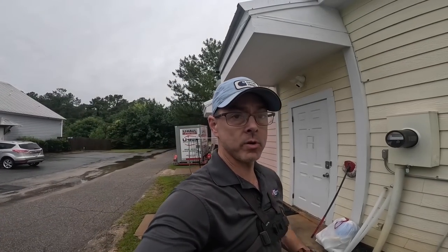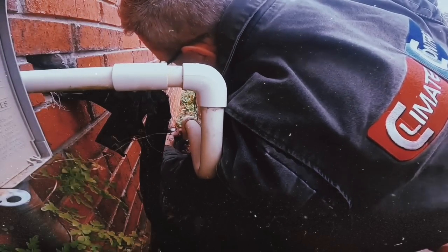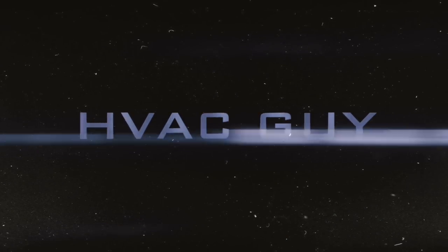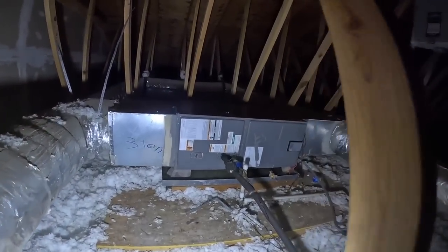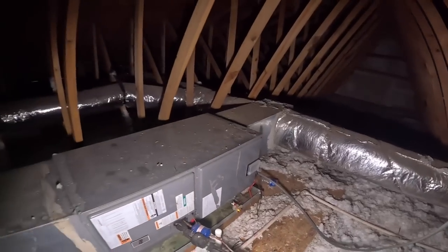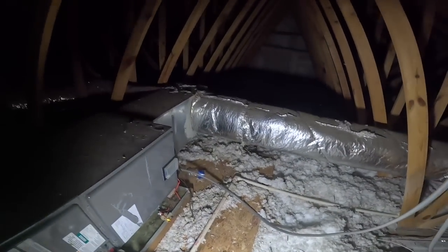Hey guys, today we've had a slight break in the rain. I've only been able to do one other call indoors — this one is running outdoors, let's check it out. I guessed right: we've got water in the emergency drain pan. This ain't the first time. Let's clear the drain — we do have a blowout right here so I can pump the water out.